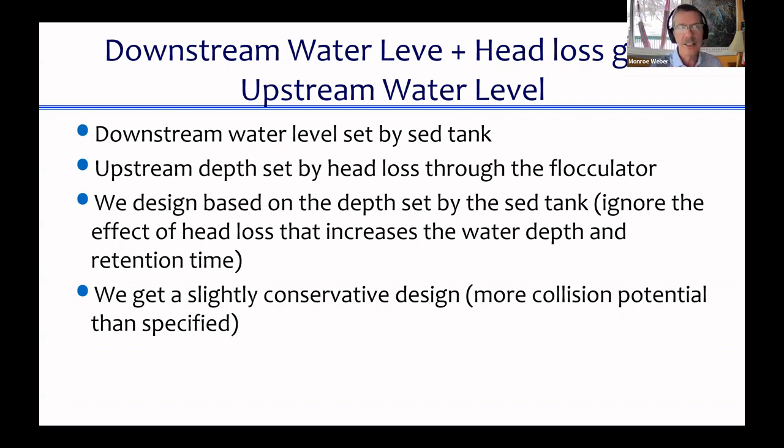So you've got to treat, oh, this might be helpful to you. I think in your design challenge, you're going to calculate how much head loss there is going around each baffle. And it's a tiny bit of head loss. And that's enough energy to make the flocs. And if you had much more energy, it would break the flocs. So that little head loss is an indication of how tiny the waterfall could be before there'd be a problem.